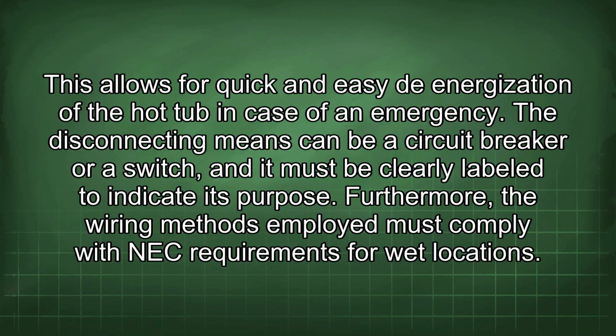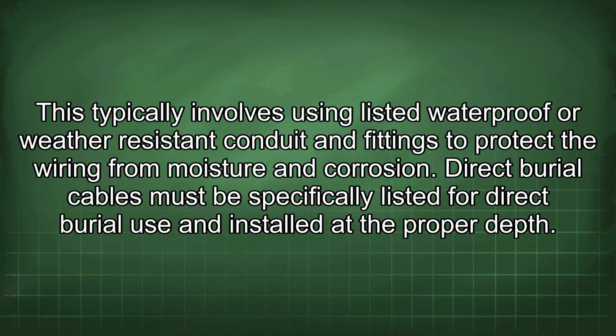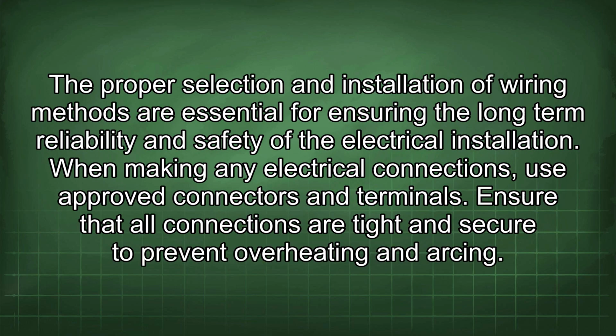The disconnecting means can be a circuit breaker or a switch, and it must be clearly labeled to indicate its purpose. Furthermore, the wiring methods employed must comply with NEC requirements for wet locations. This typically involves using listed waterproof or weather-resistant conduit and fittings to protect the wiring from moisture and corrosion. Direct burial cables must be specifically listed for direct burial use and installed to the proper depth. The proper selection and installation of wiring methods are essential for ensuring the long-term reliability and safety of the electrical installation.